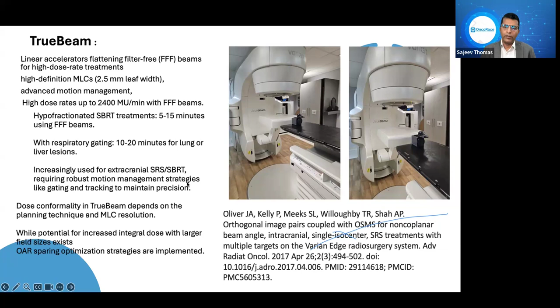So we will also have a look into the TrueBeam. TrueBeam is one of the radiosurgical platforms which is commonly used. However, the key advantage of the TrueBeam is it has a higher dose rate. So it can use the FFF beams with the high definition MLCs, and advanced motion management is also possible with the system, where the treatment time could be reduced, which is an advantage for SBRT and SRS. This is one of the advantages with TrueBeam, a linear accelerator based technology.